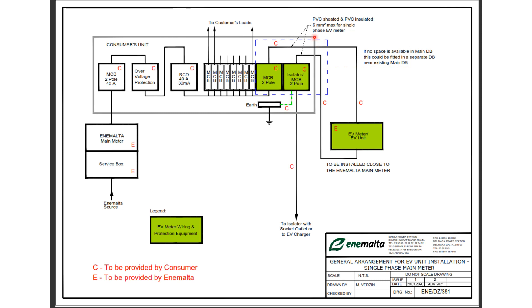So we need to have a maximum of six millimeter squared for a single phase EV charger. The six millimeter squared is basically the maximum which can be handled for a 40 amp installation. Usually six millimeter squared is associated with a 32 amp charger, so it is basically useless having anything larger than six millimeter squared.